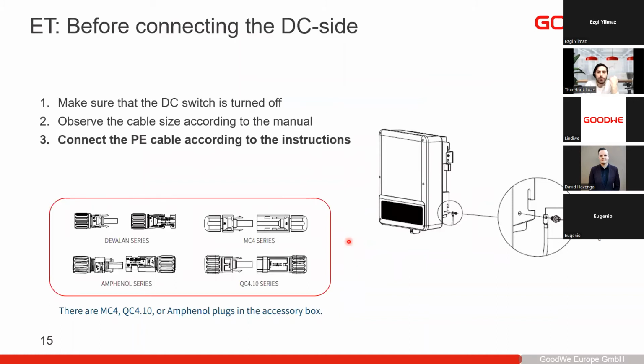Okay, so before connecting the DC side of the inverter, it's very important that you make sure that the DC switch is turned off. Then observe the cable sizes according to the manual. And then please also connect the PE cable or the grounding to the outer case of the inverter before you do any more connections.